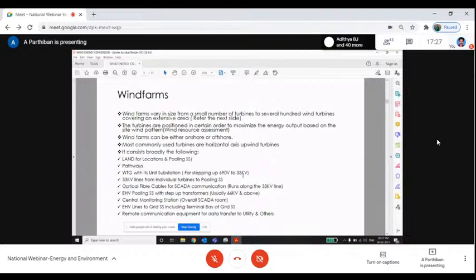So this is the form of a wind farm. And the wind farm consists of access pathways to access the WTGs for operation and maintenance. And we have optical fiber cables, because all the wind turbines are connected via optical fiber cable, that is OFC cable, to the SCADA system. For example, this 300 megawatt wind farm will have a central monitoring station at one place. From that place itself, we can monitor all these 100 turbines.